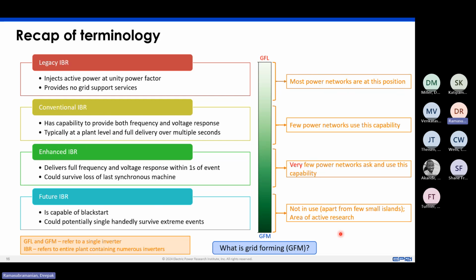That is intentional, because the idea of this kind of service from an inverter-based resource is that it should be control agnostic. It shouldn't matter whether I am running a specific type of control architecture, as long as the required service is provided to the grid. So specific elements of control systems should not define the capability of a device or the services of the device. And that leads to the question of grid forming.